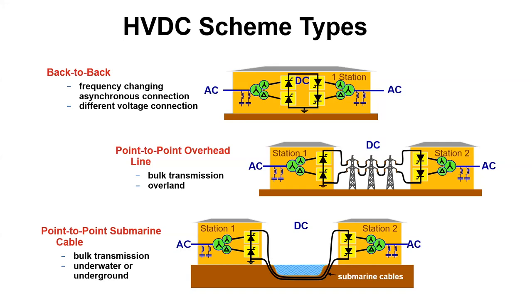The second one is the point-to-point configuration, and within point-to-point, you could have a point-to-point overhead line application, or a point-to-point submarine cable application. With point-to-point connection, it has the sending end converter station in location one and the receiving end converter station in location two, with, of course, a transmission circuit in between, connecting both stations for enabling power transmission.